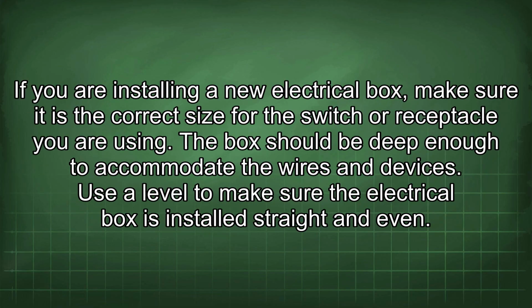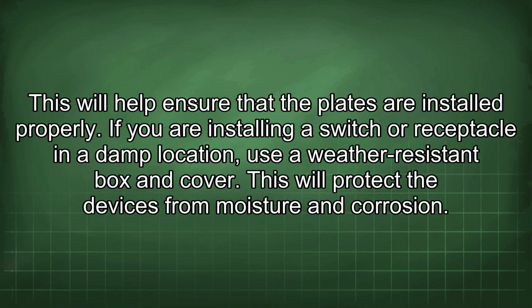If you are installing a new electrical box, make sure it is the correct size for the switch or receptacle you are using. The box should be deep enough to accommodate the wires and devices. Use a level to make sure the electrical box is installed straight and even, which will help ensure the plates are installed properly.